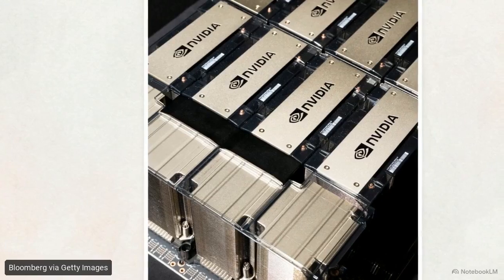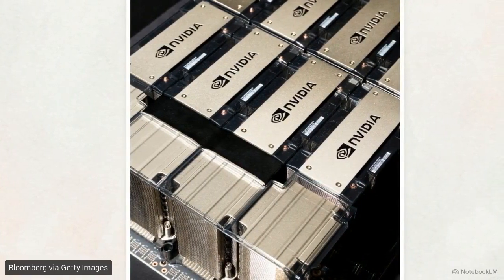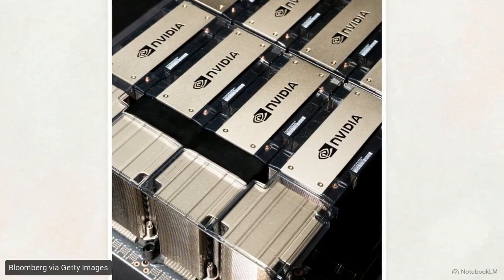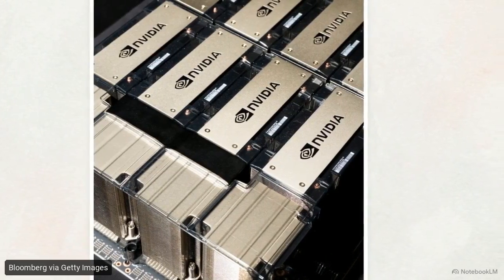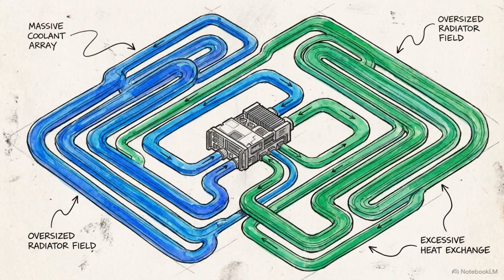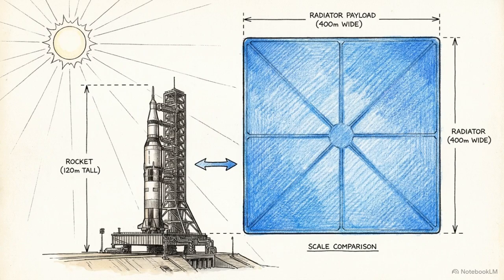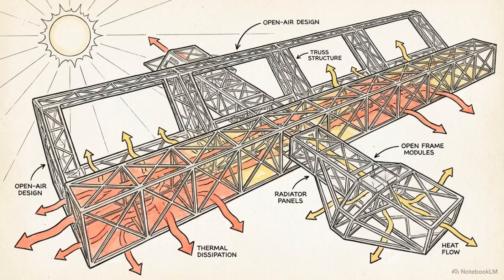Modern AI accelerators generate low-grade heat, requiring cold plates that operate between 330 and 370 Kelvin to stay within silicon reliability limits. Relying on these conventional coolant loops in space creates a massive footprint. At 330 Kelvin, the structural radiator area required to reject that heat quickly challenges the capacity of heavy-lift launch vehicles. To reach gigawatt-scale compute, the architecture must be dictated exclusively by thermal physics, rather than terrestrial server standards.